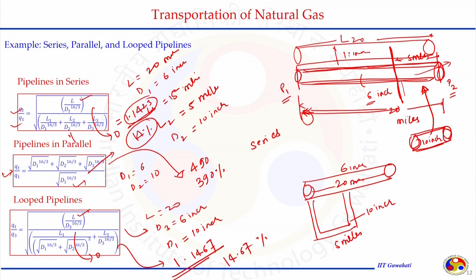And when the calculation is performed, the numerical value comes out as 1.1467. It means a 14.67% increase in the gas capacity is calculated when we have this kind of looping system. So, I think with this example, it is clear how we can perform the calculation and calculate how the gas capacity is changing when we are having the series, parallel and loop systems.